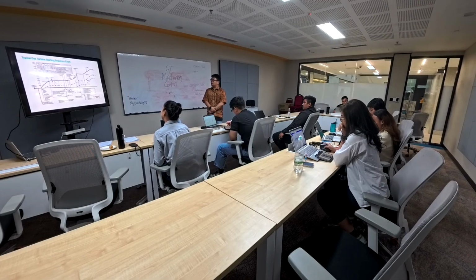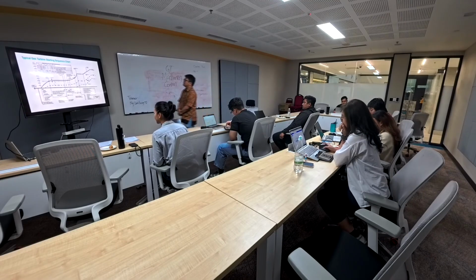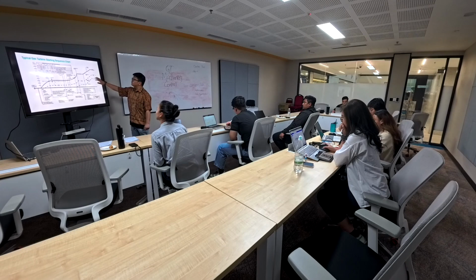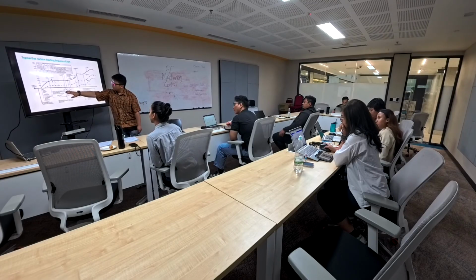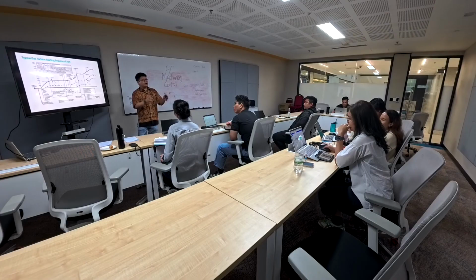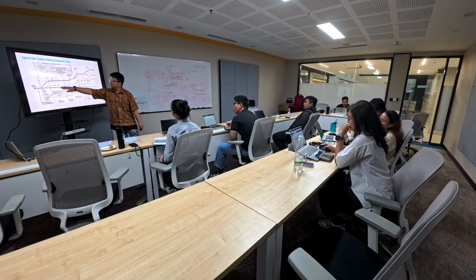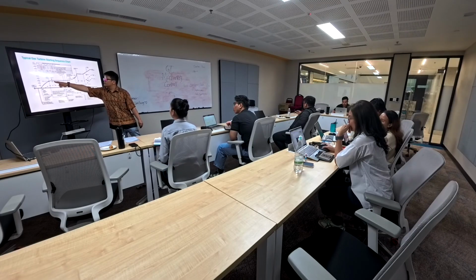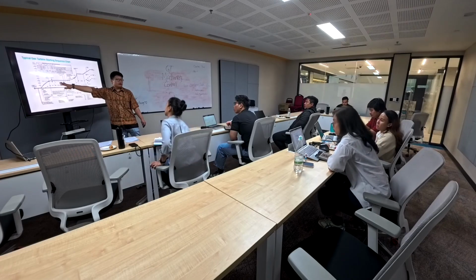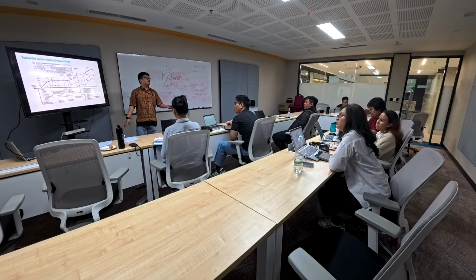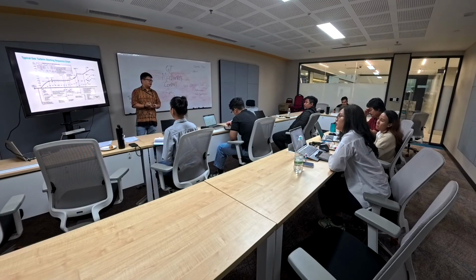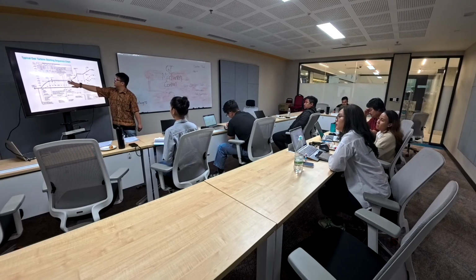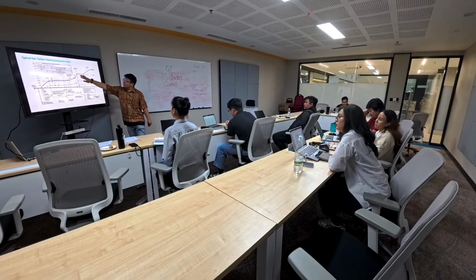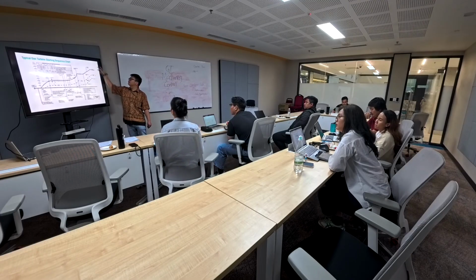Okay, this is a typical gas turbine starting sequence chart. It's in NGP, or speed, so it tells you what is typical. If I go through quickly, you will ramp up once you have done all your system checks, such as the lubrication system. It will crank your engine, so you will crank up to 2,900 or 3,000. This is the purge cycle. It will purge off the excess fuel remaining in your enclosure and in your engine. After that, you will go for ignition, then engine pull away, then your gas generator idle, and once you are at idle, normally you will stop for a while before you load. So you load, then it goes to full load.